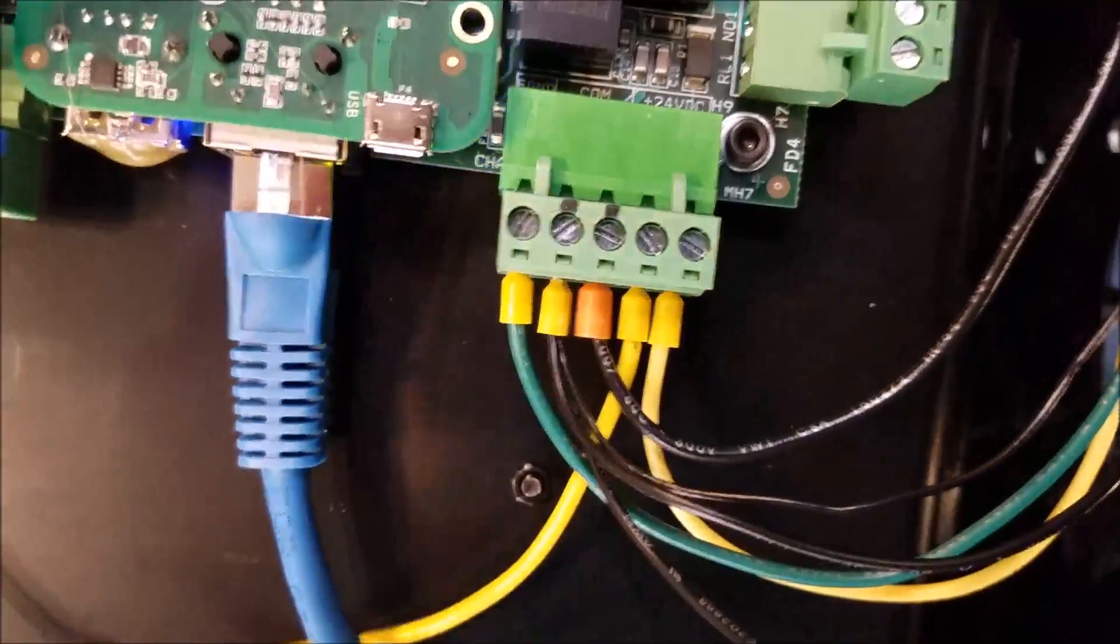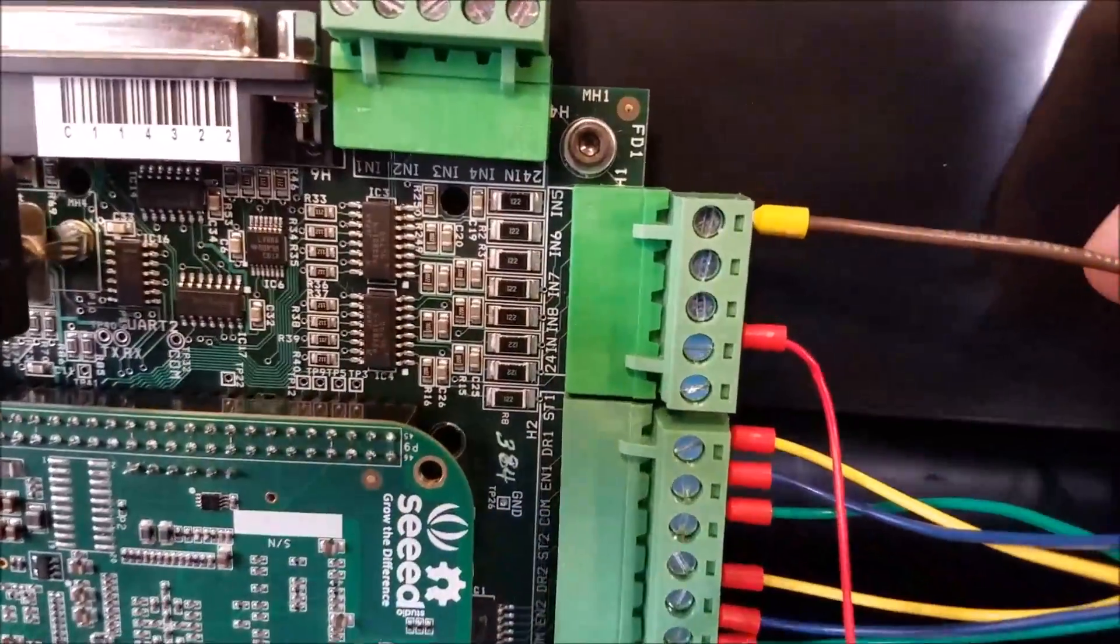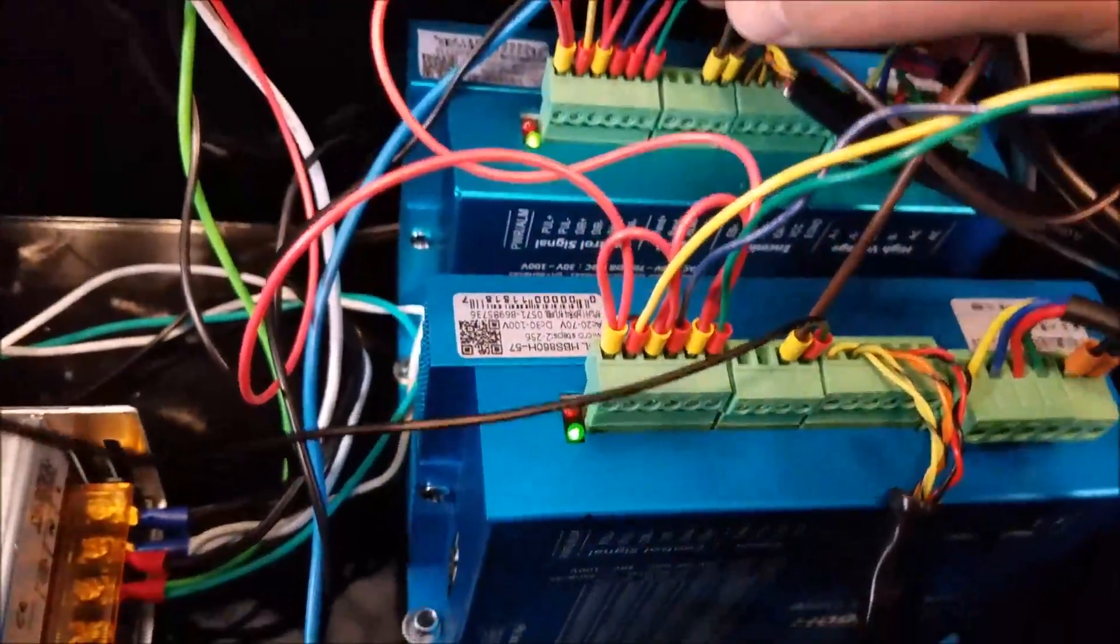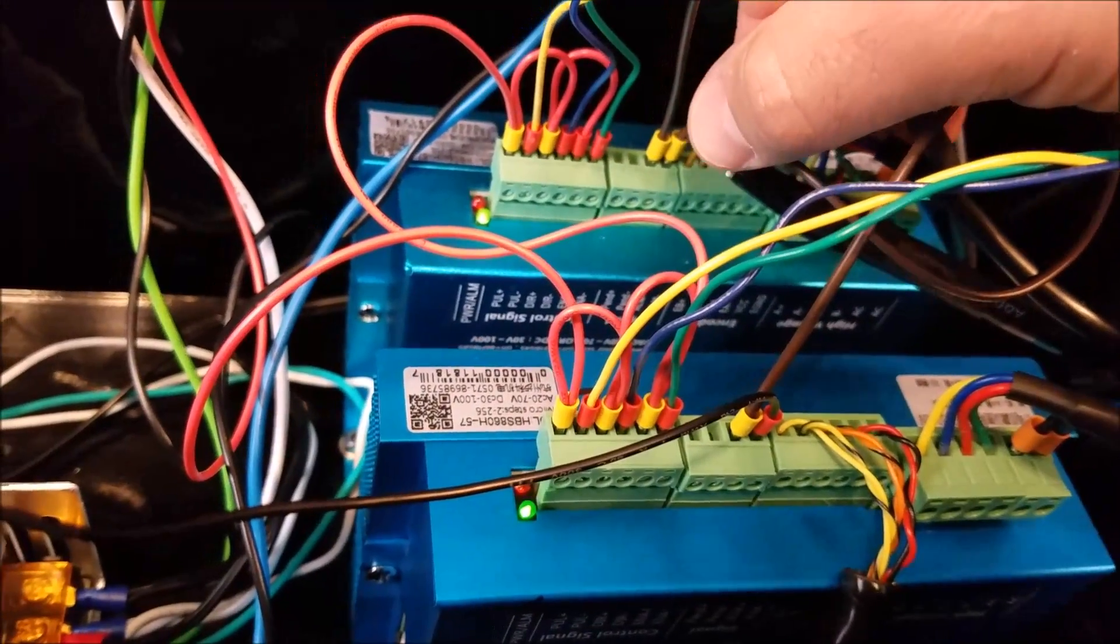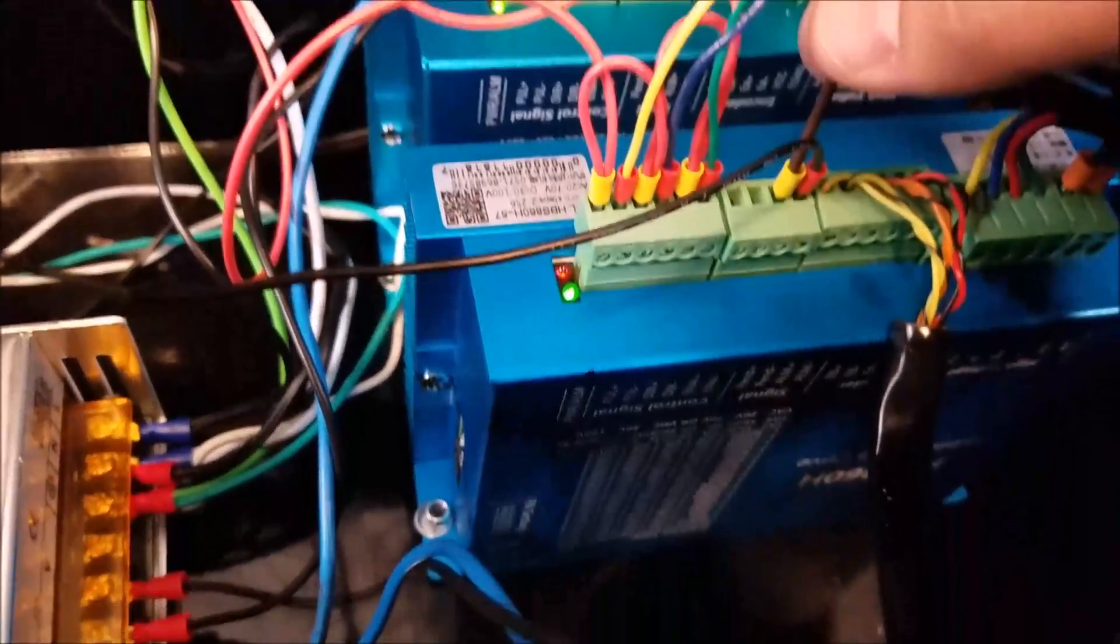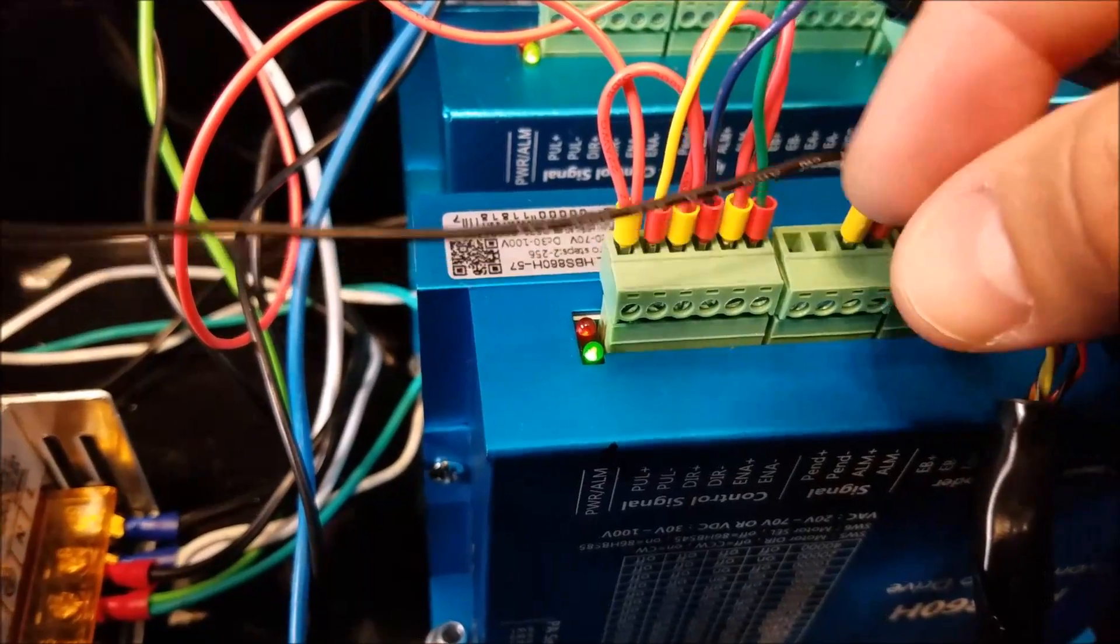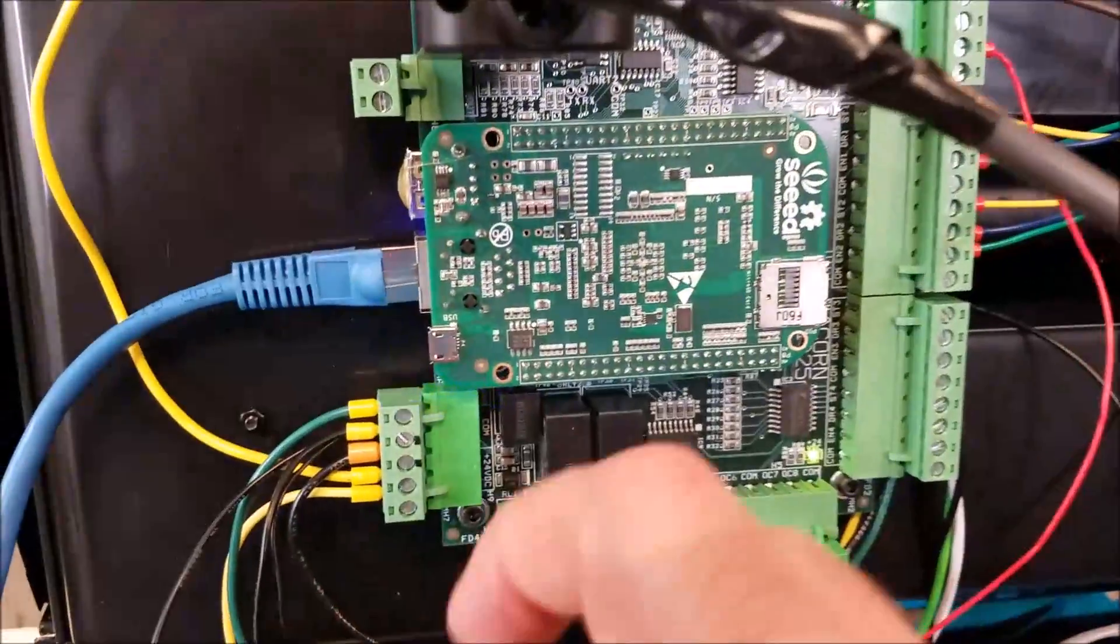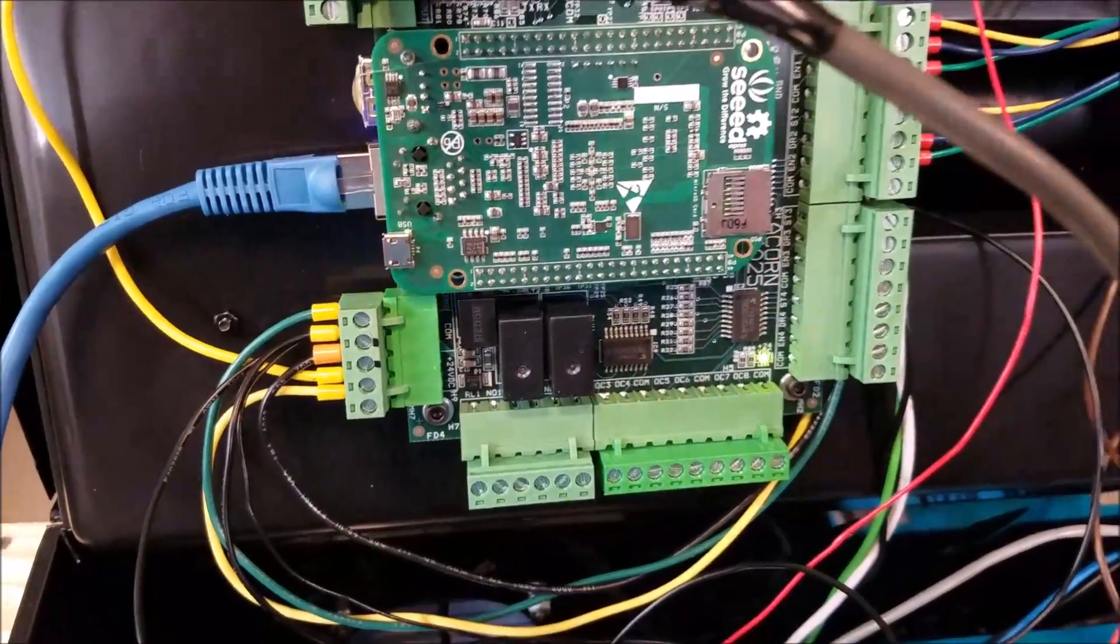So once again, just for clarity: we have the brown wire coming out of input five, feeding down into alarm positive. Then from alarm negative, we're jumping over to the second drive, wiring it into the alarm positive. And then we're taking alarm negative all the way over here to common.